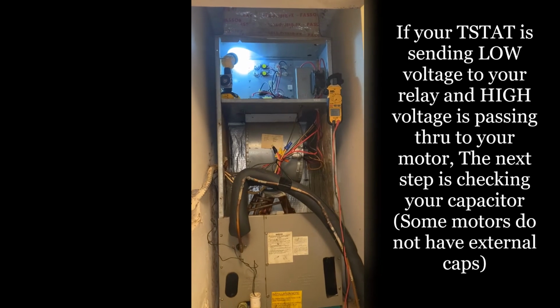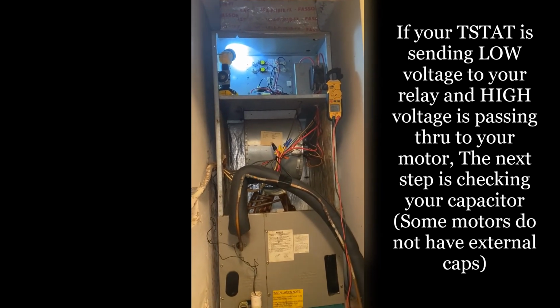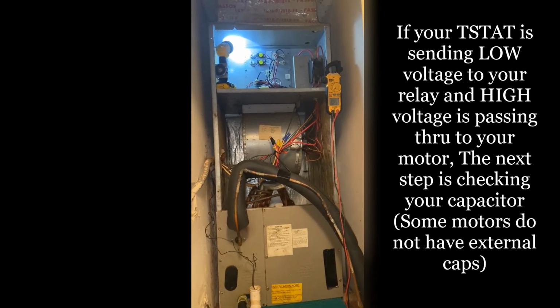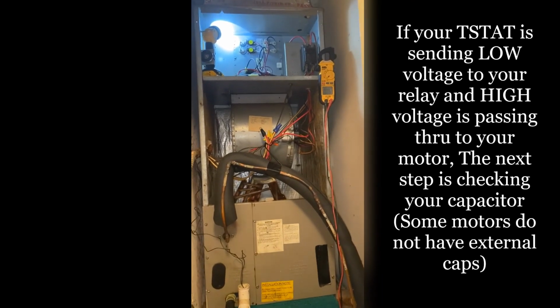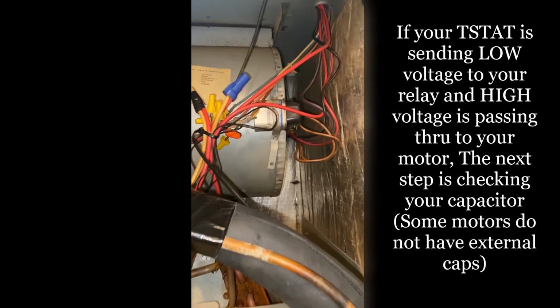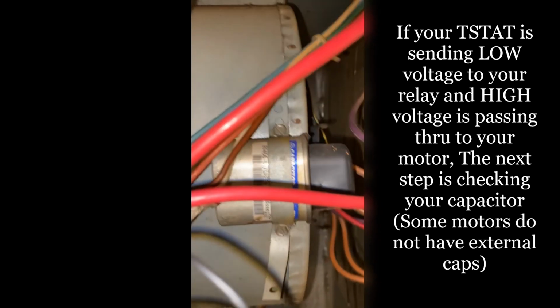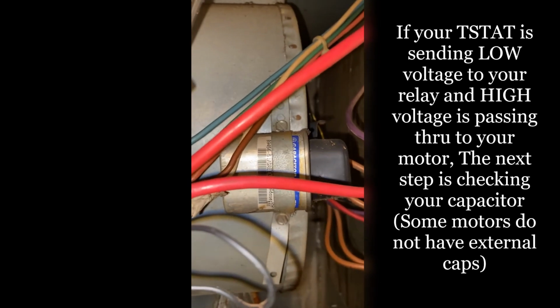So we checked and we have high voltage, low voltage. Our relay is closing, but our motor still is not running. The next step would be checking the capacitor. If you have a capacitor in your evap fan, that would be the next step. So let's do that.